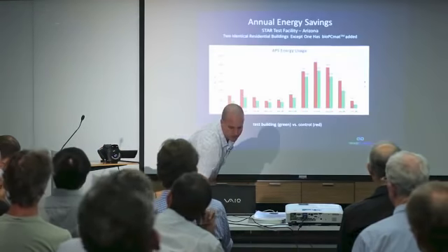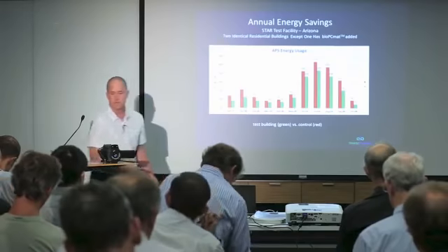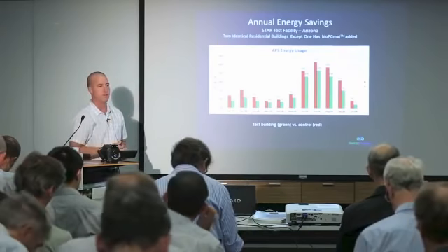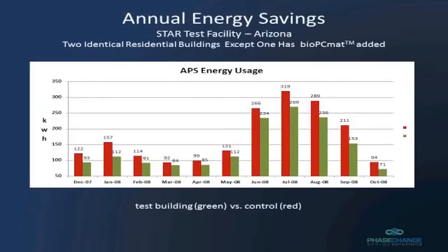If you look on the back of your brochure, you'll see that there's a measurement at the bottom of the table of each of the different columns, which is kilowatt hours per square metre. Can everyone see that? So kilowatt hours per square metre is how much energy you have to put into the material to get it to transition from frozen solid to be totally melted. So if you look at, let's say, the middle product in the middle column, because it's easy to find.